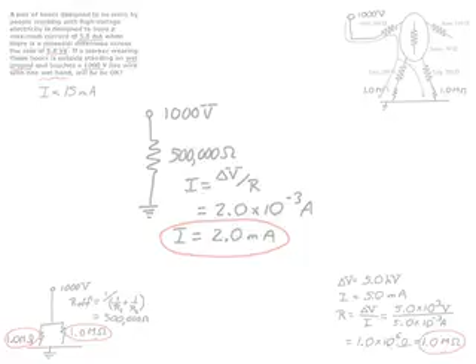But let's take a look at our result and see if this makes sense. We came up with a final answer of 2 milliamps. If we look at the table of safety values for working with electricity, for AC, the threshold for sensation, where you can just feel it, is about 1 milliamp. So in a situation like that, wearing the boots, worst case scenario, if you touch the wire, you'd feel it, but it's well below the threshold for causing physical problems. You'll feel it, but you won't be injured. You'll know you're touching a live electric wire, but it won't hurt you, so you can take steps to rectify the situation.